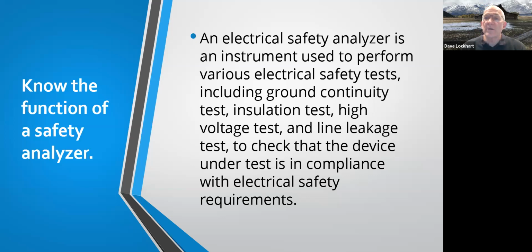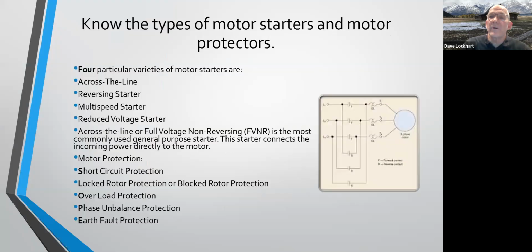So electrical analyzer is a simple test piece of equipment that you can plug a piece of equipment into, run it through its test, and make sure the equipment is safe for operation. So hopefully you're very familiar with it, but basically what you're going to be testing for is the ground continuity, insulation, high voltage leakage or high voltage test, and line leakage test is probably a big one there. So that's where we'll use electrical analyzer to make sure that everything is safe, wired properly, and functioning.